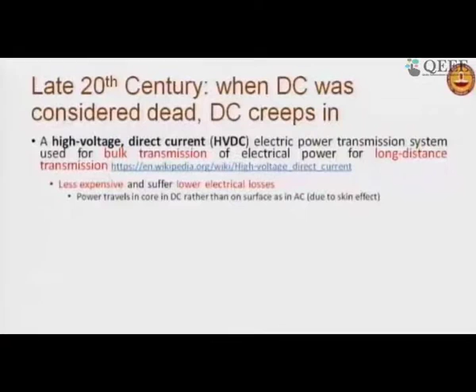Why? It turns out DC is less expensive with lower electrical losses, because of something called the skin effect. AC at high voltage tends to get transmitted more on the outside core of the conductor and doesn't use the whole conductor. If it doesn't use the whole conductor, the copper it sees is less, so resistance is more. DC, on the other hand, is transmitted throughout the conductor, sees the whole of the copper, and the losses are less. Once this was realized, people started using it, especially for long distance transmission where losses can be high.